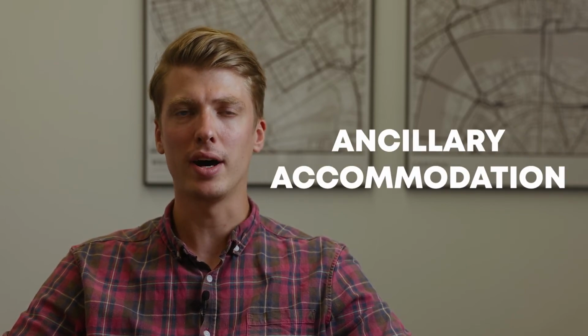Now for the penultimate piece of jargon in today's video, ancillary accommodation. These are the parts of a building that aren't part of said building's main purpose, so they're ancillary to the overall use of the building, but remain under control of the premises. To be clear, some examples of these spaces are refuse areas and bicycle storage. These spaces typically require 0.4 meters squared of natural ventilation, but ducting this to the outside takes up a lot of ceiling space, which is very precious. What we'd often do to get around the problems in these tight spaces is to install an equivalent amount of mechanical extract, but of course, every project is different.